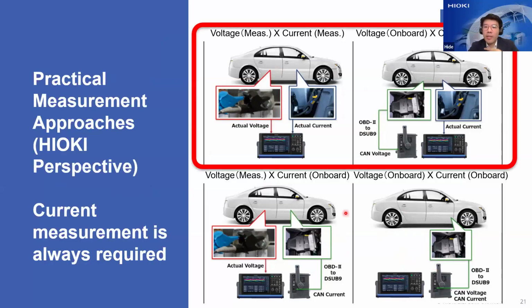HIOKI considers 2 approaches realistic for power measurement in EV testing. One is the traditional way with both actual voltage and current measurement. The other recommendation is onboard voltage (CAN voltage) combined with current measured using a current sensor or clamp sensor. In both cases, we recommend using current sensors.